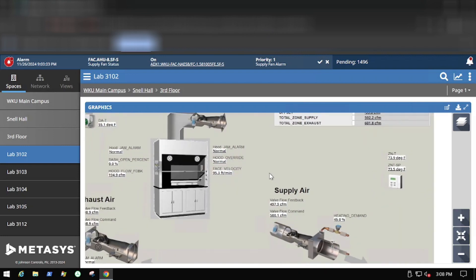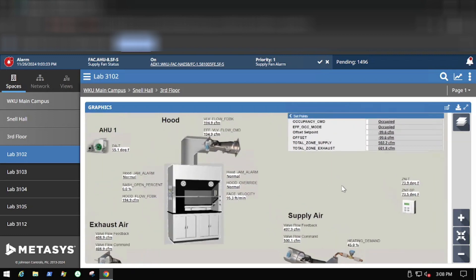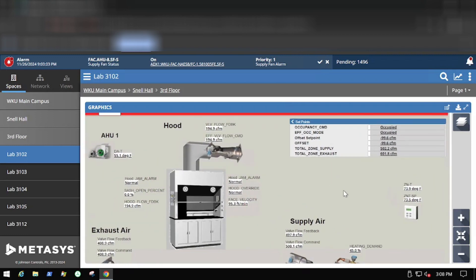We also need to remember that when we're pulling air out in a building with both negative-pressure labs and normal rooms, the air handler serving the normal rooms has a lot of extra work to do. You do not want to pull the entire building negative, because that will cause problems with humidity and other issues. You need to maintain your air handlers carefully — we'll look deeper into that in just a few moments.